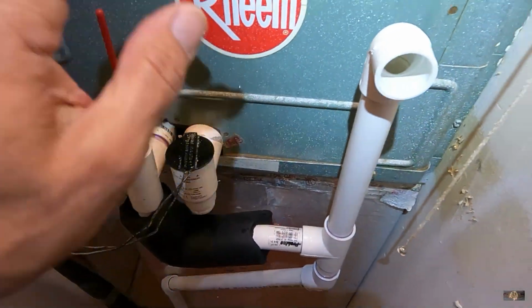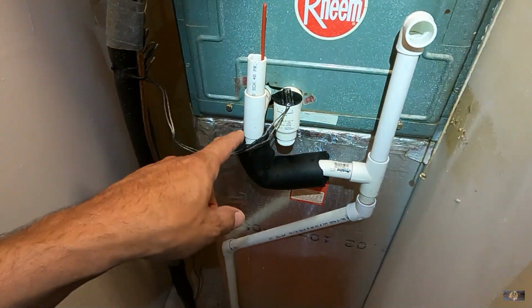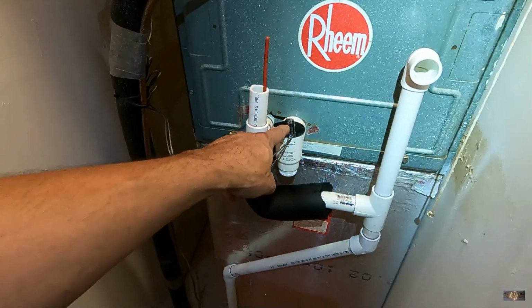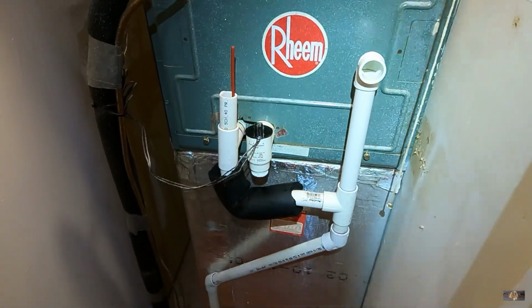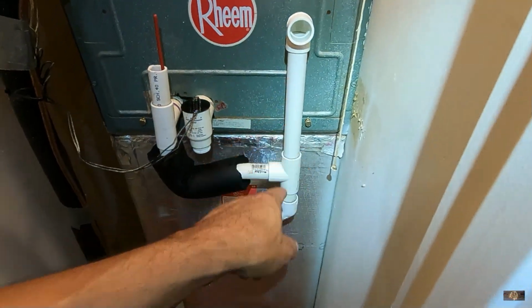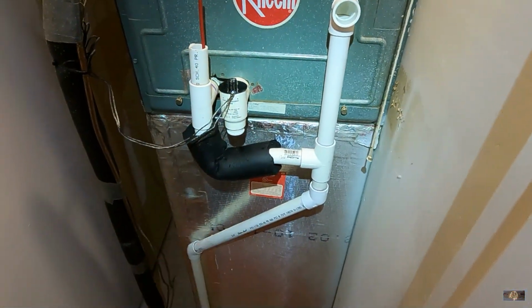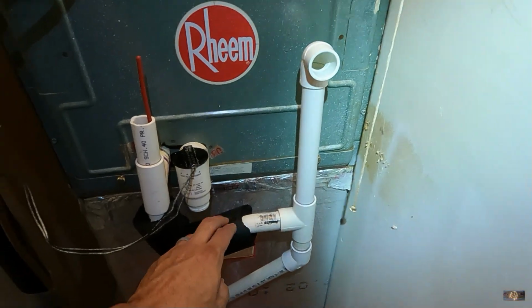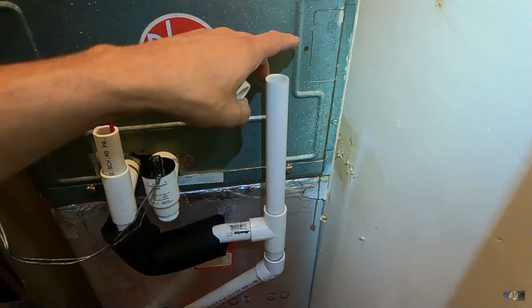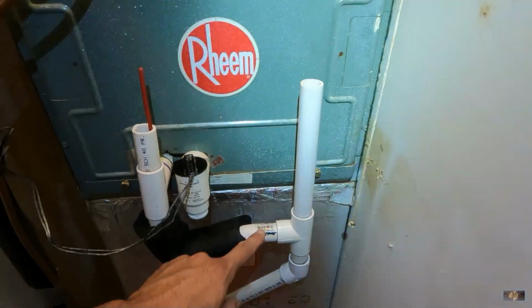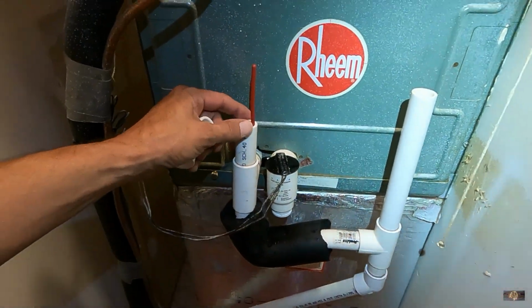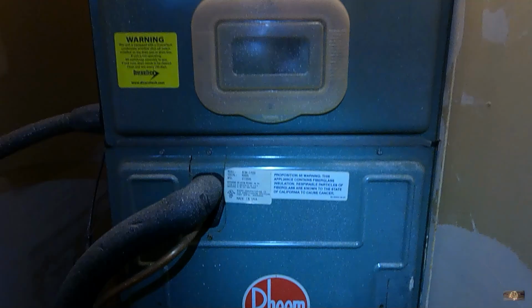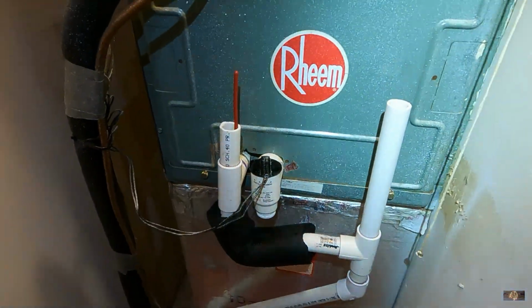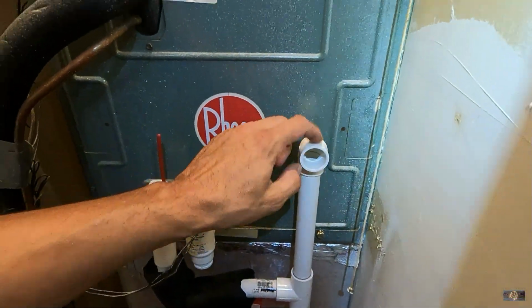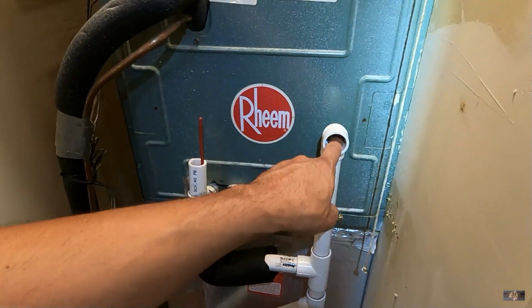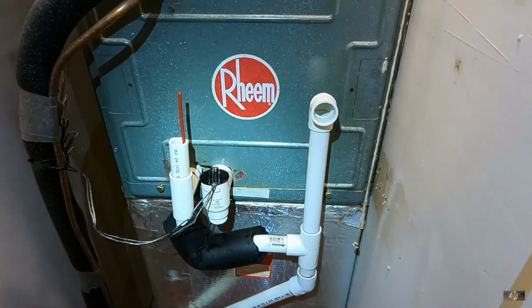I actually ran this drain right here. Originally it didn't have a clean out for the trap, and it didn't have any float switches, so I installed this CS1 float switch, and I put 45s in the vent on it. So when you pull a vacuum outside, if you want to get this done, you just pop that off and put a cap on this, and it'll pull through all the way through this trap. This normally has a cap up there, and it'll pull through the whole thing. That's why I left this off, but I put a 90 on the vent because I don't want debris falling down in it.